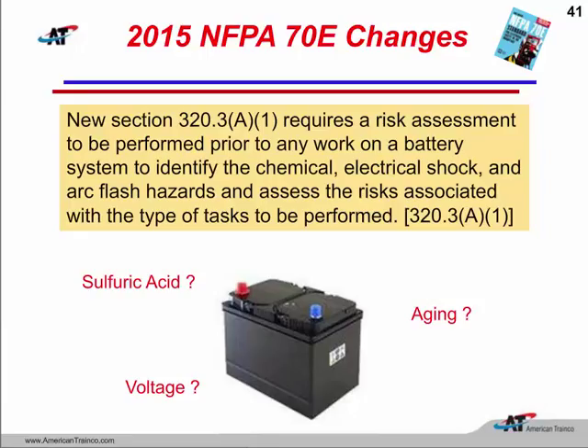We ought to have a little bit of an idea if the batteries have been maintained properly. And in any risk assessment, I would also throw in there to make sure that the air has been circulated properly in that room before we allow a worker to enter that room. So Chapter 3 deals with all of our special equipment. Lasers would be in Chapter 3. Electrolytic cells and research and development labs would be up in Chapter 3. Also, we would see our power electronic equipment, VFDs, up in Chapter 3 as well.